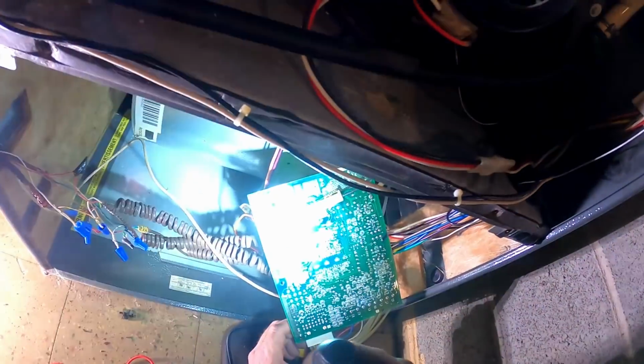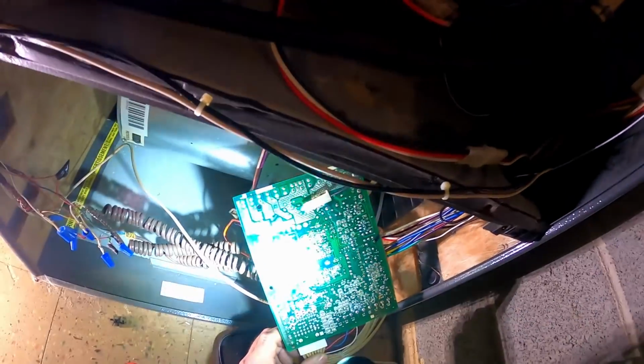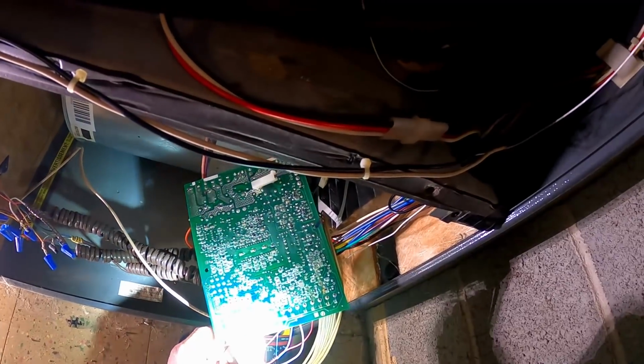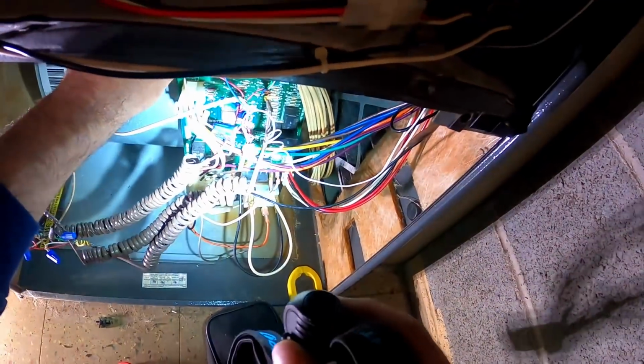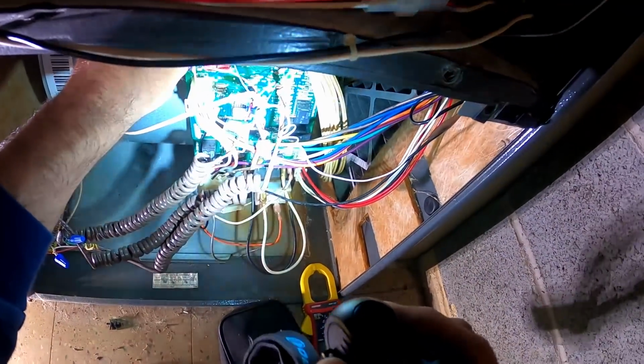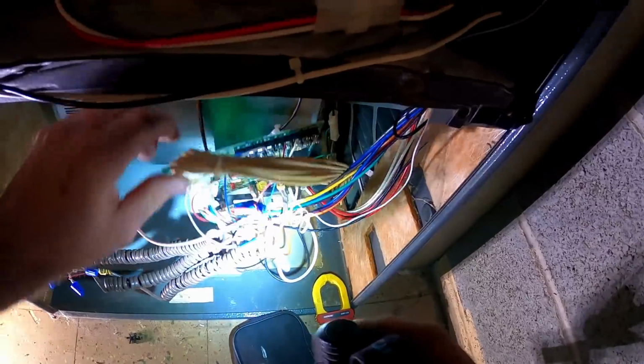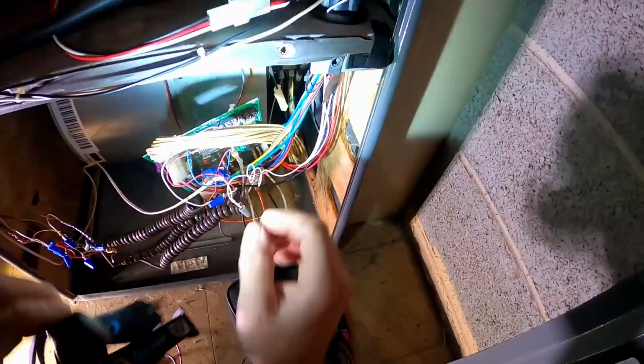So I got power, 24 volts going into it. I got 24 volts at the fuse, and I got nothing at the terminal strip. So it is a bad control board.